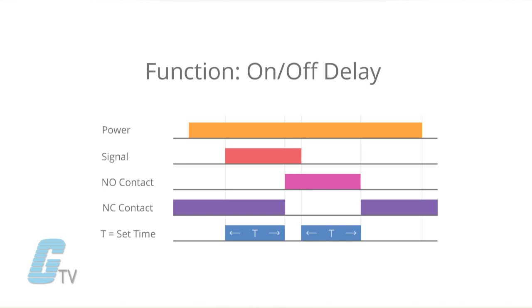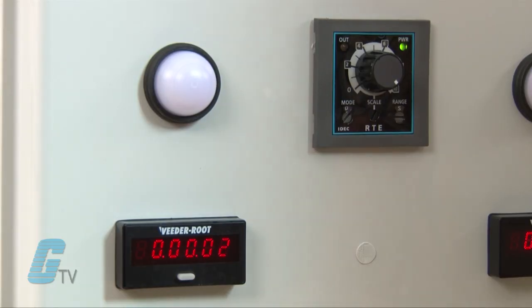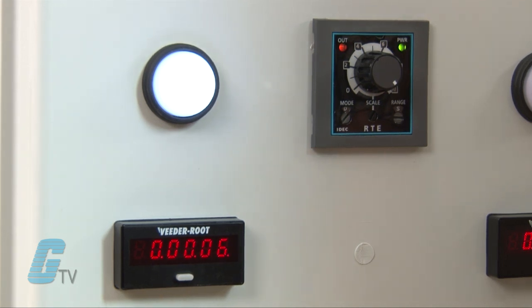This timing function can change from device to device, but generally starts with an on delay function when the signal is applied. If the signal is a momentary signal, it can be set up to begin timing when the signal is supplied and then set to an off delay when the signal is applied again. Maintained operation signal starts may have the on delay function start and then trigger the off delay function when the signal is no longer applied.